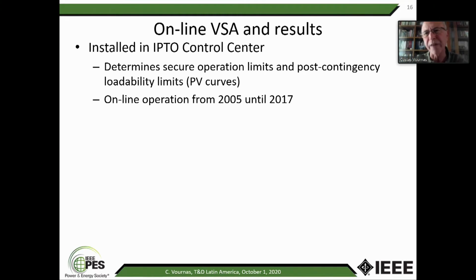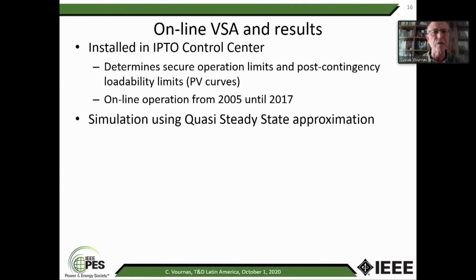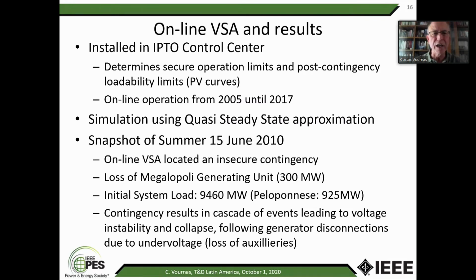As you understand, it was immediately after the blackout that this was installed. And this gives you the results in the form of the PV curves that I showed before. But if you have only one load, it's very easy. If you have many loads, you have to define how you want to show the results. So what we are using is PV curves of a part of a system, in which case we call it the regional PV curve, or national PV curve, which is the total load of the system. So the simulation is again the QSS I was speaking of before.